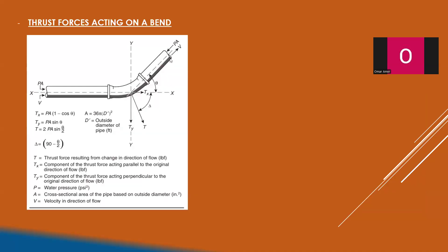As shown here, the thrust force generated at the elbow point increases with the bend angle. Also, if the pressure of the flowing fluid inside the pipe is high, it will increase the thrust force. The velocity of the flow and the bend angle, as mentioned, also increase the thrust force.